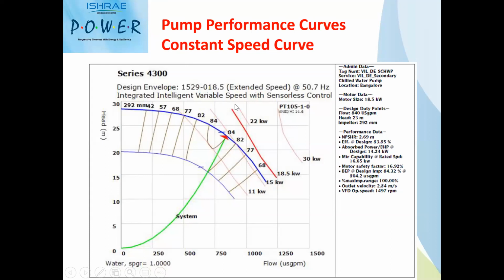As I told, flow decides the size of the pump, which is 6-inch here in this case, and head decides the diameter of the impeller. So based on this, typically we have selected this pump for 840 US-GPM at 23 meters head.